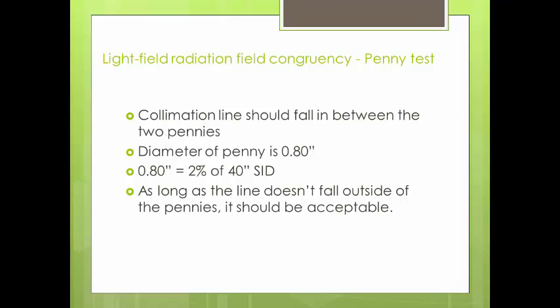If on any one of your sides you can see both pennies in their entirety, your test is not acceptable. You need to contact either your engineering department or the manufacturer, and someone needs to come adjust your collimator.